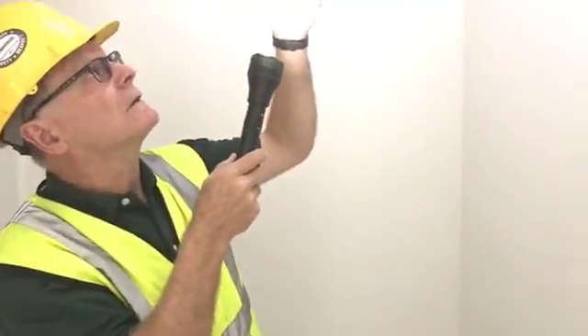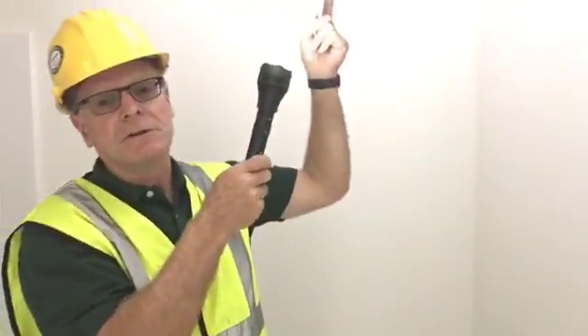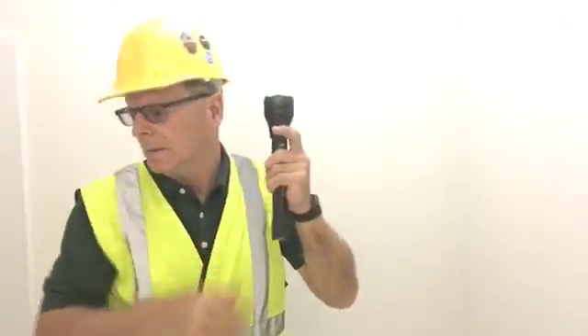They have passed the initial test. We have to wait for the electrician to hook up the timer so we can actually test the continuous rate. We made some other adaptations in our ceiling for this mock-up. We sealed areas in the floor, and to simulate what we're doing with air leakage from the shower enclosure, we've taped that up to simulate that this is finished.